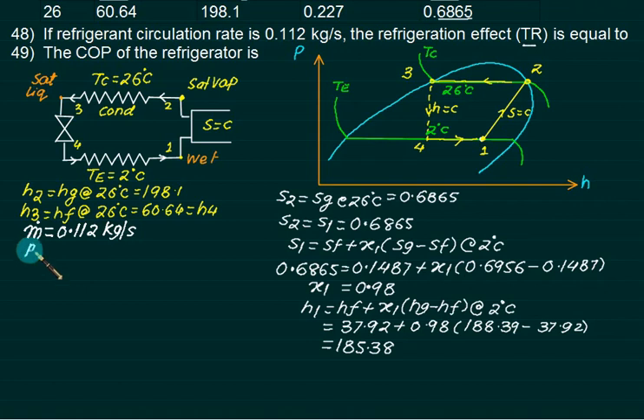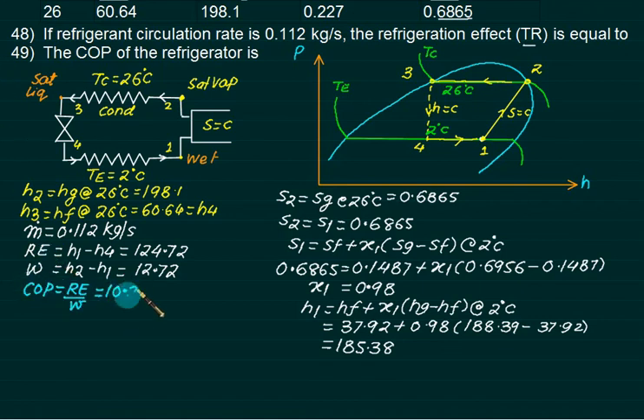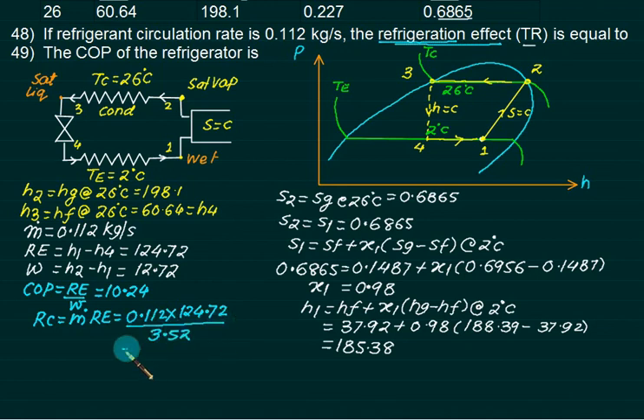First we calculate Re, then W. Re is H1 minus H4 for evaporator, compressor work is H2 minus H1. We know Re and W. COP is Re by W, which is 10.24. Refrigeration capacity Rc is m dot multiplied by Re. M dot is 0.112, Re is 124.72. He is interested in tons of refrigeration, so we divide by 3.52, giving approximately 4 TR.